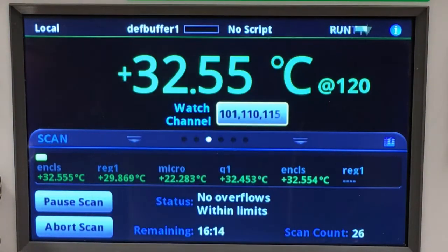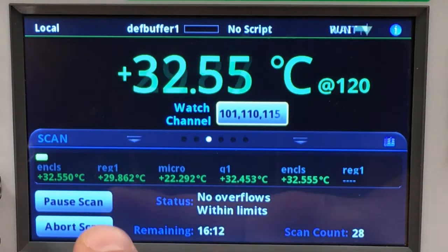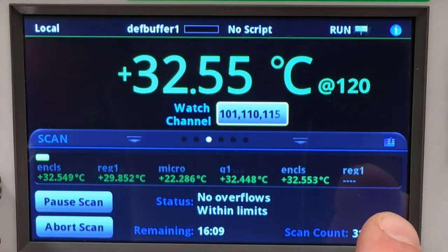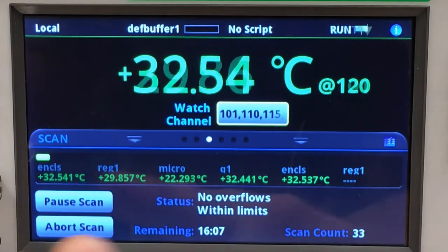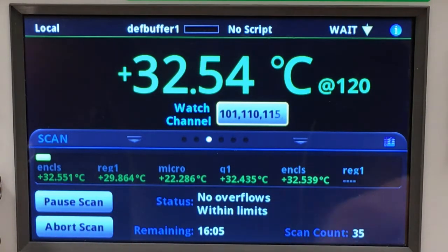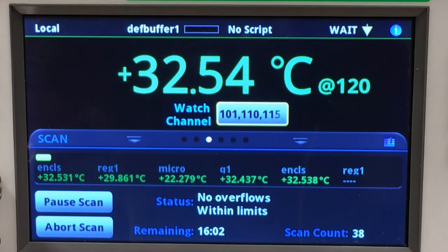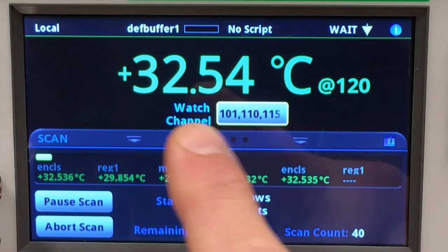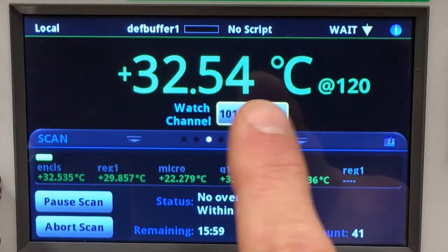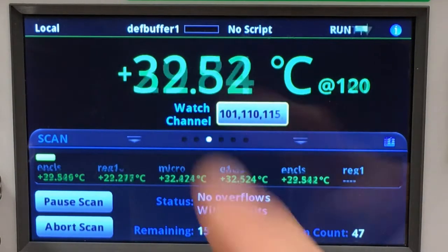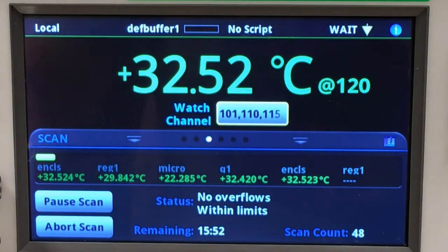Channel 120 is still selected by default. I accept. Now you can see that the carousel is monitoring each of the four channels and letting us know by the label that we applied what measurement goes with what channel. You can also see in the measurement window that as the instrument takes measurements for each individual channel, those are displayed in the main area.